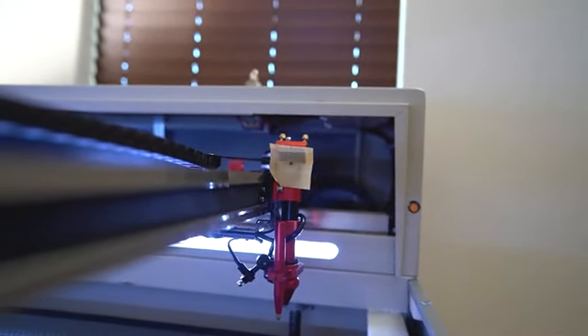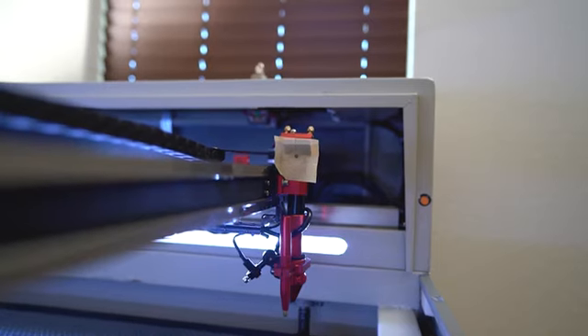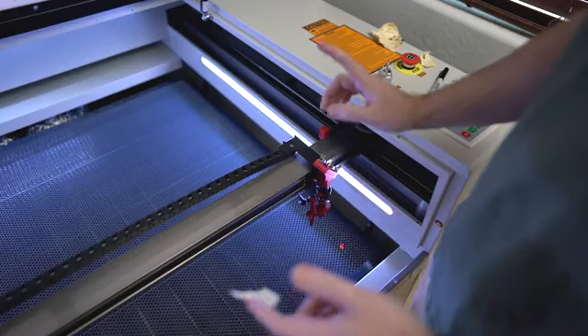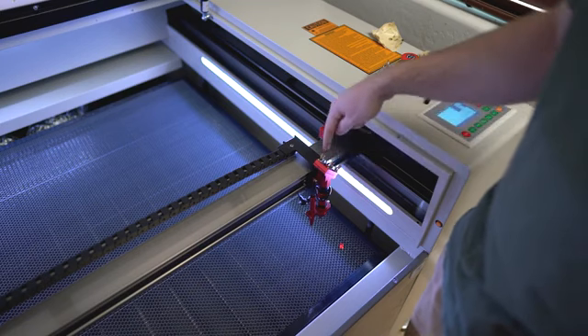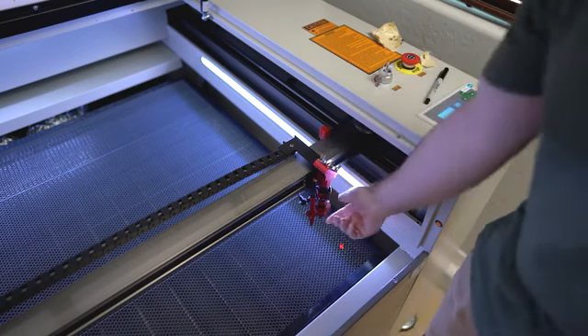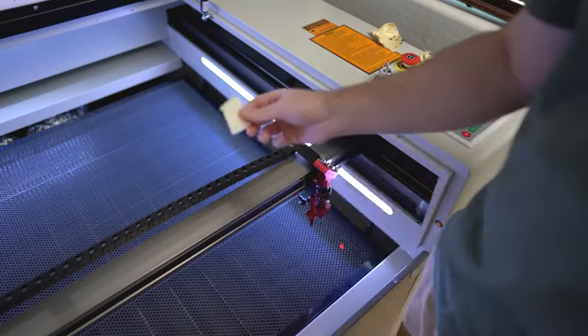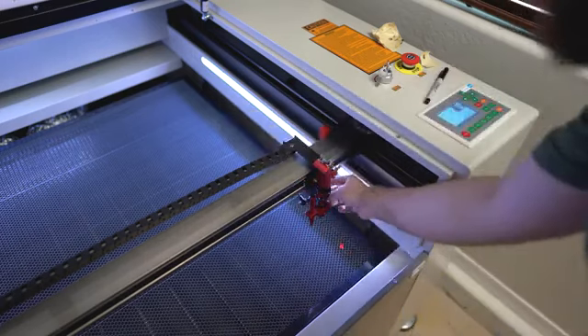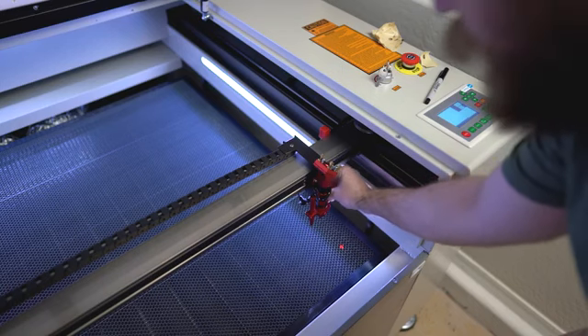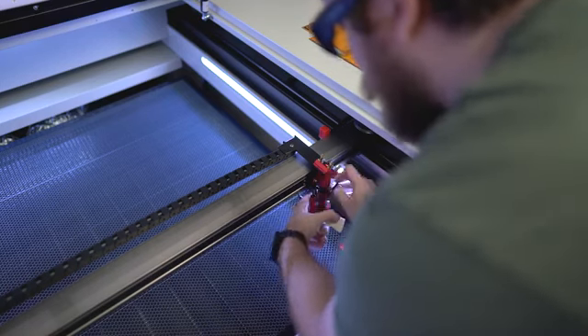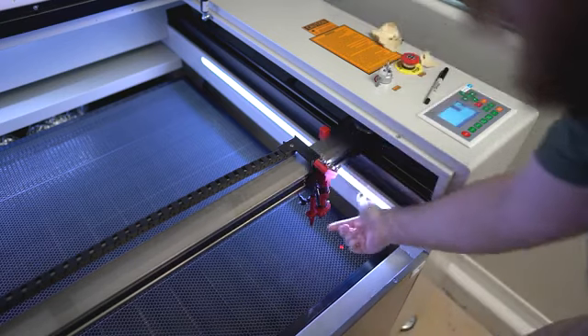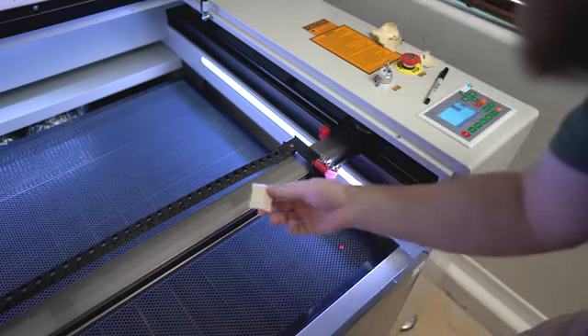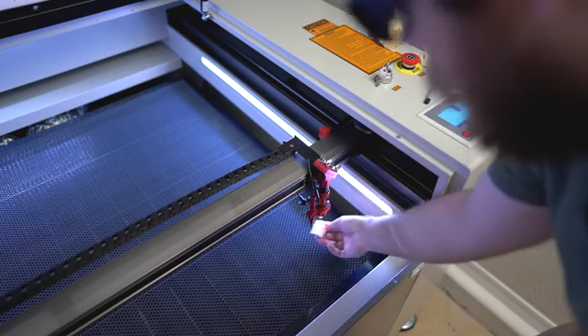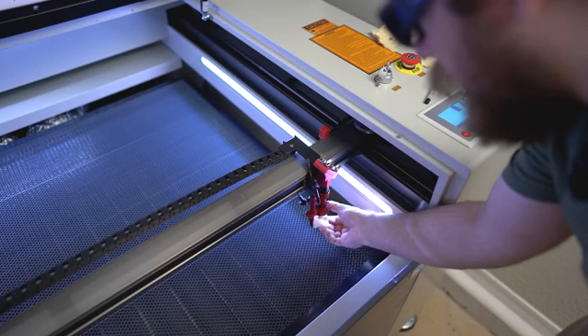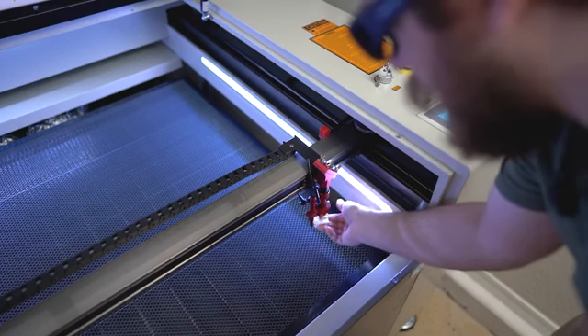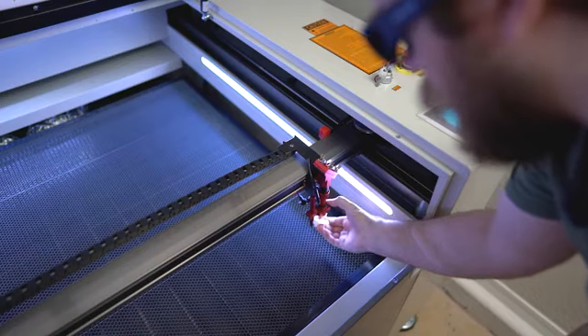The next step is to make sure that the mirror on the laser head is coming out of the nozzle in the center. Let's get to that. With all the other mirrors dialed in, there's only one last one to consider, and that is the mirror that directs the beam down into the lens and through the bottom nozzle here. So what we're gonna do is apply a piece of tape to the bottom. You might want to disconnect your air assist if you can't get the tape to stick, because the air is constantly pushing out of this nozzle and it might prevent this from sticking. So we'll undo that for now and stick your tape to the bottom of the nozzle and press hard so that you get an indentation of the edge of that nozzle.